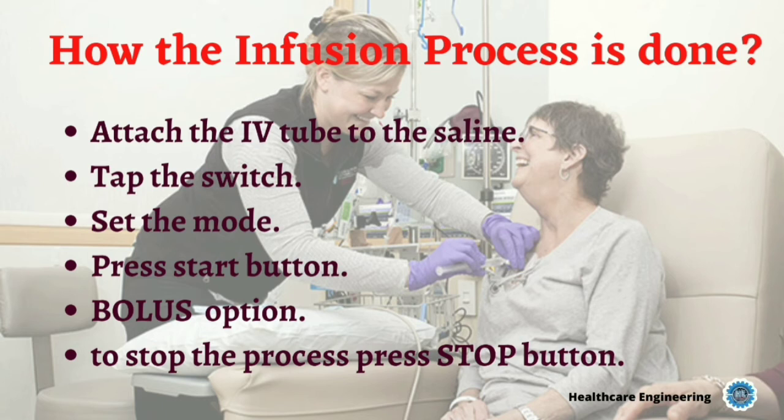Depending on the model of the infusion pump, you can then set, as the next step, a specific volume in a specific time, so that the rate is automatically calculated and displayed on the screen. And you can also set the rate directly. After finishing all these settings, press the start button to start infusing the medication liquid.